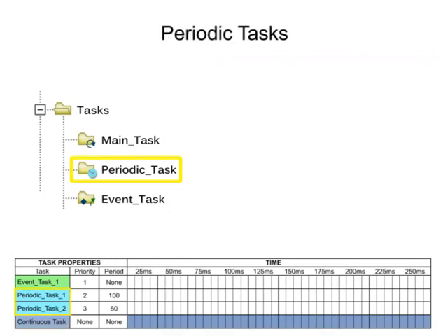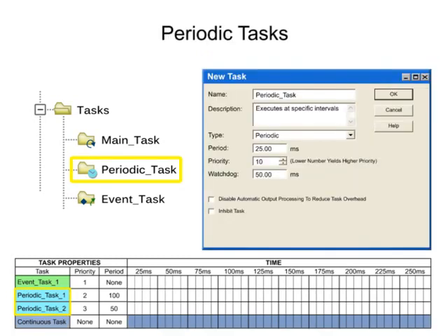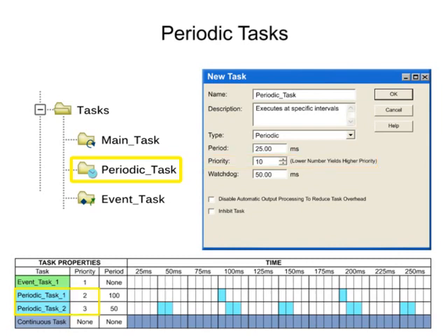Periodic tasks perform a function at a specified interval. Configurable time periods range from .1 milliseconds to 2000 seconds. Priorities assigned range from 1 to 15, with 1 being the highest priority, and are necessary for scheduling when multiple tasks are used.